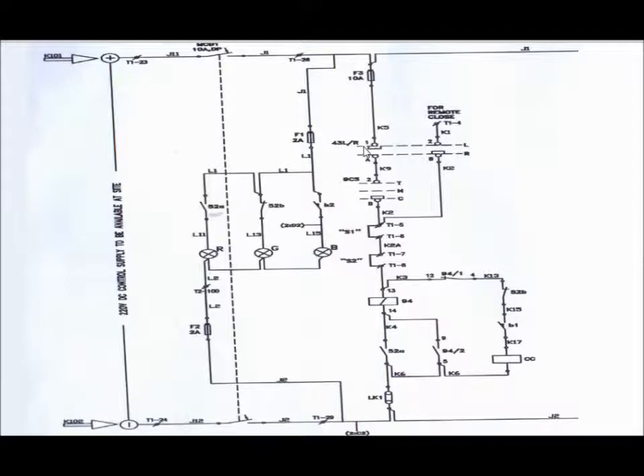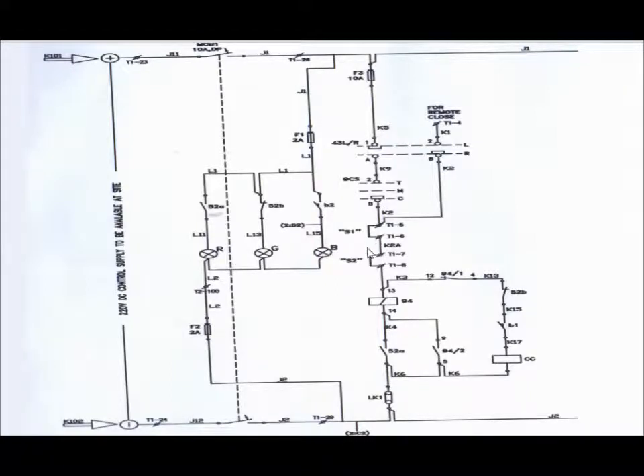43 LR is the contact of the local-remote selector switch, and 9 CS is the closing control switch located at the circuit breaker. 94 is the anti-pumping relay of the circuit breaker. There are two interlocking contacts which must be in shorted condition if no interlock has been taken.